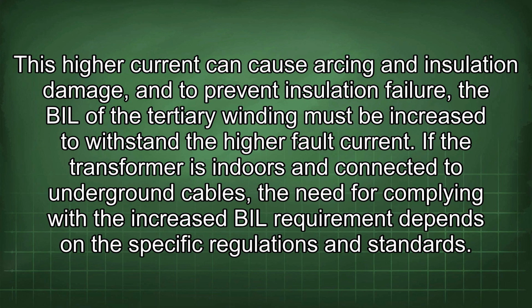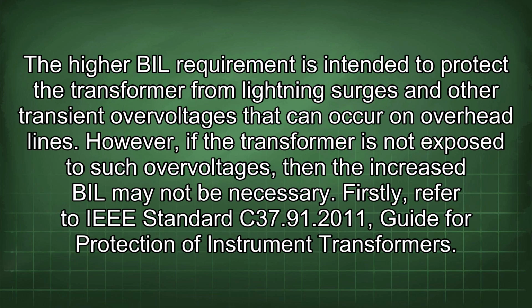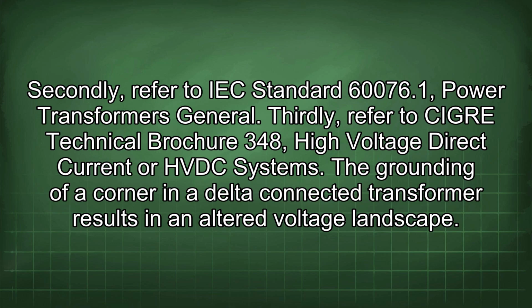If the transformer is indoors and connected to underground cables, the need for complying with the increased BIL requirement depends on the specific regulations and standards. The higher BIL requirement is intended to protect the transformer from lightning surges and other transient overvoltages that can occur on overhead lines. However, if the transformer is not exposed to such overvoltages, then the increased BIL may not be necessary. Firstly, refer to IEEE Standard C37.91 2011, Guide for Protection of Instrument Transformers. Secondly, refer to IEC Standard 60076.1, Power Transformers General. Thirdly, refer to CIGRE Technical Brochure 348, High Voltage Direct Current or HVDC Systems.